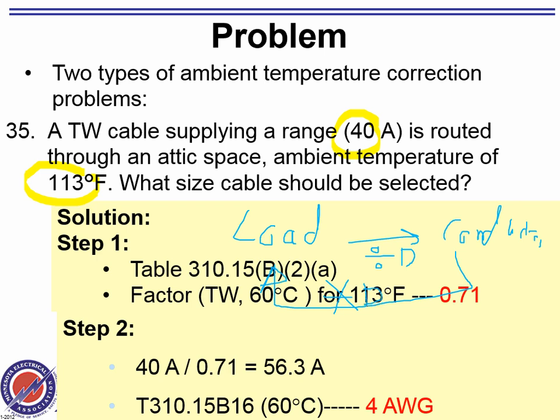Now, once you get to 56.3, which column do you want to go under, 310.15(B)(16), and why? You need to go to the 60 column. Why 60? Why not 90? Well, the conductor is TW. So it will be number 4.